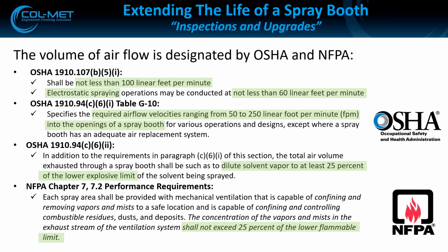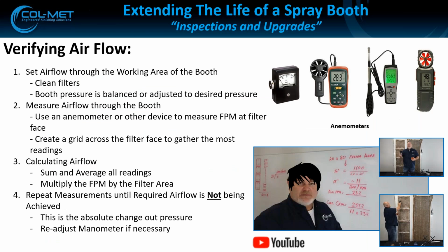This is a step that needs to be done as soon as the booth has been erected for the first time. That way you have that baseline and you know that your booth is performing as it should. As the booth ages and you keep performing these tests, if it starts to degrade in its airflow, then you're going to know that something's happening, and we'll talk about some of those reasons here. That's why it's important to understand how the booth was designed originally and why. As you move from a new booth to a 2, 3, 5 or 15-year-old booth, you have a baseline to go on.